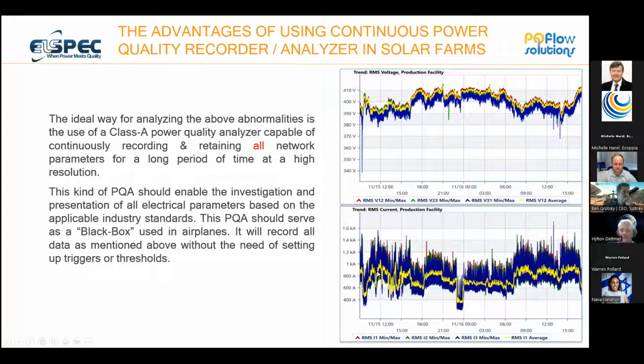However, when you take a cycle-by-cycle recording, you're sitting at almost 1.7 kA on this installation, and the voltage is dropping below the 370 mark. So it's imperative to understand the network in a cycle-by-cycle manner. Traditionally, you have to tell the instrument what you want to see on the network, but we're not clever enough to know what's going on at every point in the network. The instruments need to be able to tell us this.